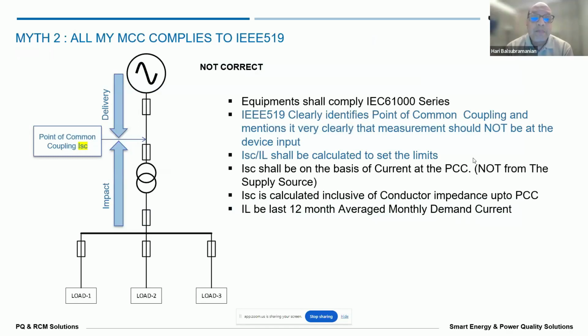All my MCC complies to IEEE 519. This is another myth. An equipment manufacturer would say, I comply with IEEE 519, which means they consider no other loads, only one load, which is their equipment at the point of common coupling, and that is clearly defined to be within the range. But that should not be calculated that way. It should actually be according to IEC 61000-2-4. So that's the second part of it, because these are all basic information which I thought I should give.